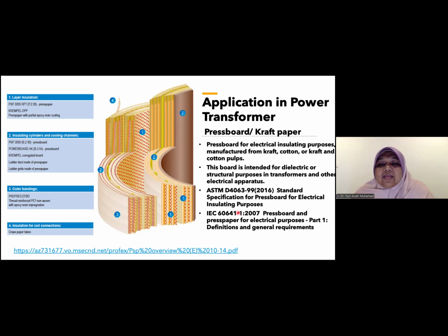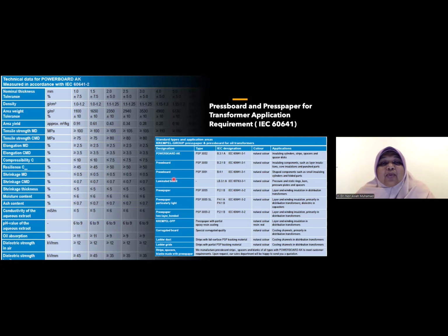There are a few standards that we can refer to, which is ASTM D4063 and also IEC 60641-1 for the pressboard selection and also pressboard requirements. So this is an example. If you buy the material, they will give you the pressboard application required according to IEC. So the thickness tolerance, the density, the weight. For us, the important ones are the dielectric strength in air, dielectric strength in the oil, and oil absorbency. We don't want the pressboard to be unable to absorb oil. So there are standards listed for the kraft paper to choose for the equipment.